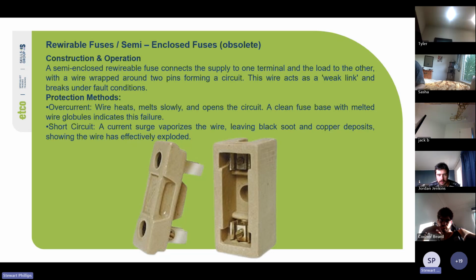So construction and operation. A semi-enclosed rewirable fuse connects the supply to one terminal and the load to the other, with a wire wrapped around 2 pins forming a circuit. This wire acts as a weak link and breaks under fault condition. So protection methods, overcurrent. The wire heats, melts slowly and opens the circuit. You can tell it's been an overcurrent issue because a clean fuse base with melted wire globules indicates this failure. Short circuit, a current surge vaporizes the wire, leaving black soot and copper deposits, showing the wire has effectively exploded.